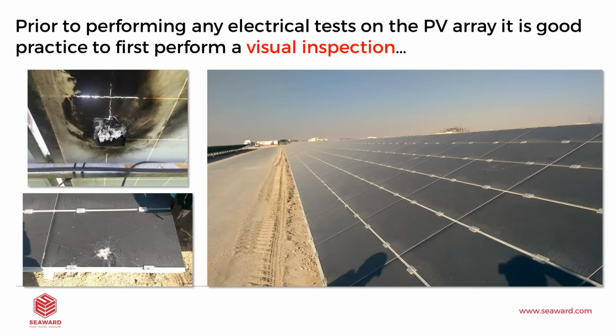So prior to performing any of the electrical tests, we should really do visual inspection. And this is a site out in the UAE. It was a very large site. It was 260 megawatts. And I was testing on this site and they were having a lot of problems. And you can see just by looking at it, the panels are very dirty. You can also see the tire treads just down to the left of the panels.